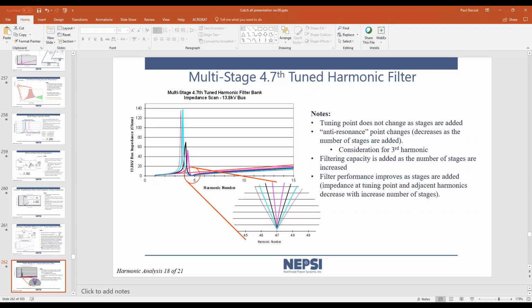And you can see here that by defining my first filter as 4.7th, I have precluded resonance at the higher frequencies, and as a result, I am not concerned about those. The resonances that do occur as a result of the installation of these harmonic filters are at a tuning point below the 5th, and generally speaking, and this is not always the case, in arc furnaces, for example, there will be harmonics, but generally the case, there are no harmonics below the 5th harmonic. You have 3rd harmonics, but they tend to be zero sequence and also not of concern.